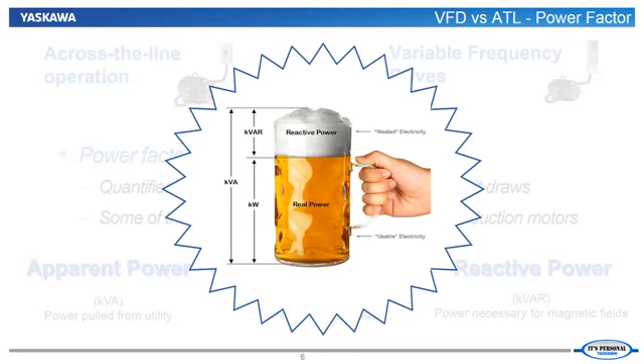How and why reactive power, or kVARs, are a reality when considering how power is drawn by an induction motor or VFD can be thought of like pouring beer into a mug. To get the beer from the keg into our mug, we would prefer that most of the contents stay in their drinkable liquid state, but some of it will become a foam head. We do our best to limit the foam, but some amount of foam is inevitable. Equivalently, we would like all of the power drawn from the utility to go to driving the load, but unfortunately, some of the power is lost to reactive elements in our system.